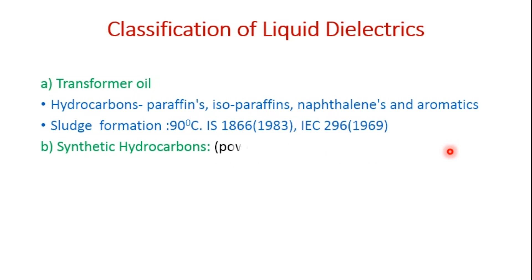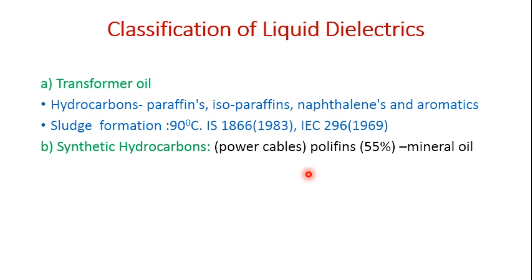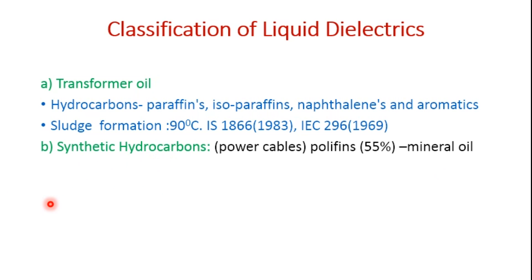The second type is synthetic hydrocarbons, which are used generally in power cables. Polyolefins are the dielectric of choice for applications in power cables — over 55% of the synthetic hydrocarbons produced worldwide are polyolefins. These exhibit the same properties as mineral oil.